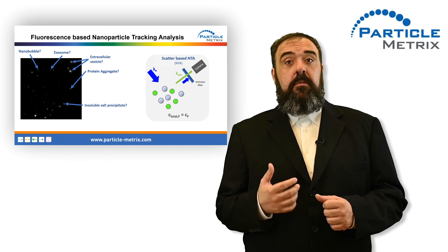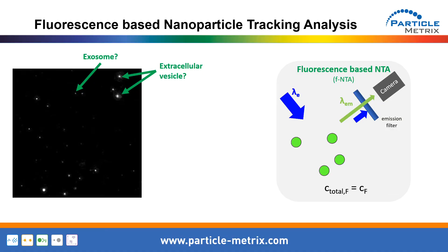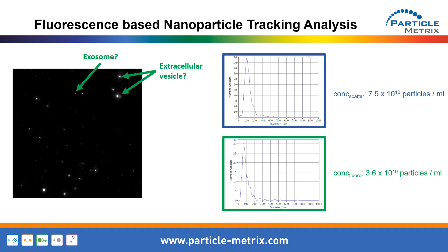This is where fluorescence nanoparticle tracking becomes important. By applying a suitable fluorescence emission filter into the scatter light path of the CW optics, the user blocks all unspecific scatter light and only the Stokes-shifted fluorescence emission light reaches the optical sensor. In this way, non-fluorescent particles will not be detected and therefore are no longer part of the evaluation. By measuring and comparing the non-fluorescent and fluorescent data, concentration ratios can be calculated and the influence of the non-fluorescent particles on the size distribution will be eliminated.